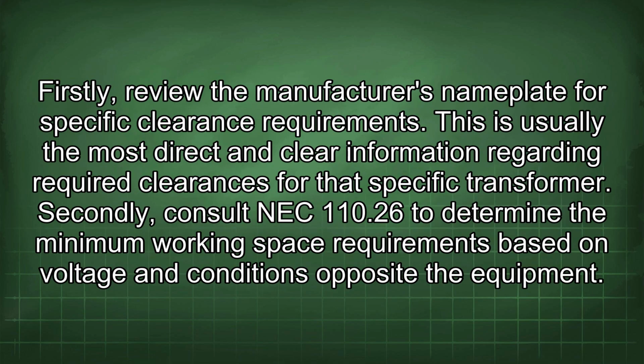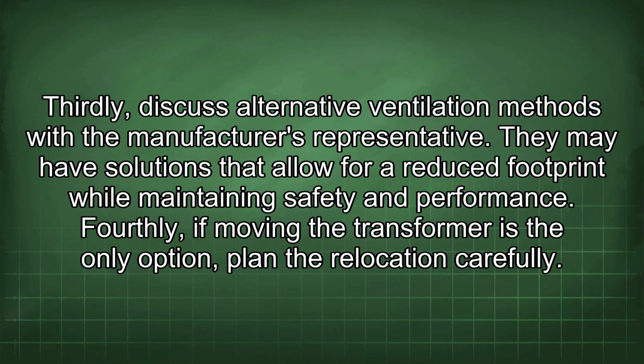Firstly, review the manufacturer's nameplate for specific clearance requirements. This is usually the most direct and clear information regarding required clearances for that specific transformer. Secondly, consult NEC 110.26 to determine the minimum working space requirements based on voltage and conditions opposite the equipment. Thirdly, discuss alternative ventilation methods with the manufacturer's representative. They may have solutions that allow for a reduced footprint while maintaining safety and performance.